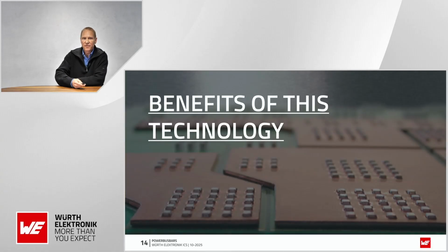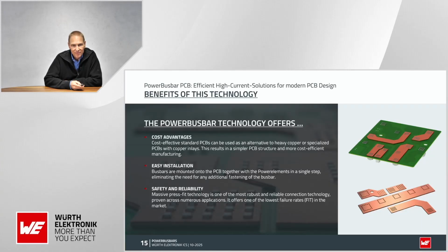What are the benefits of this technology? The PowerBusbar technology offers, at first, cost advantages because cost-effective standard PCBs can be used. There is no need for many copper layers and no need for copper inlays.